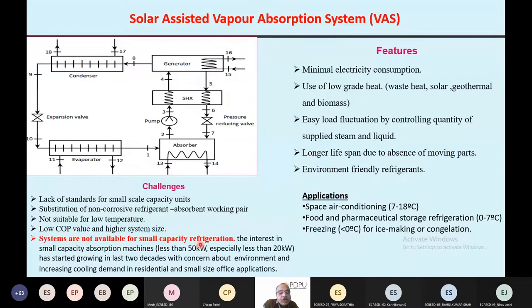The minimum size of this system is around 30 kilowatt or about 10 ton systems. Still, within those applications, space air cooling works very well. Food and pharmaceutical applications from 0 to 7 degrees can utilize it. But for freezing and ice making, it cannot be used because of the low temperature limitation as far as the operation is concerned.